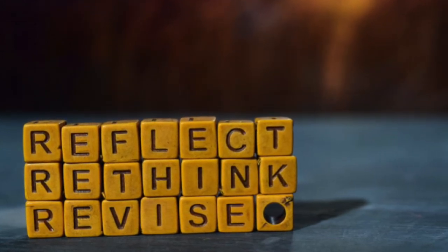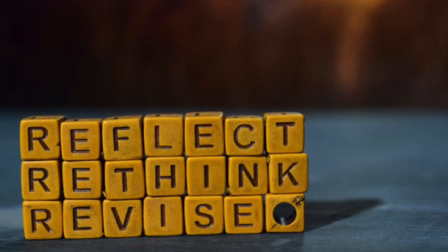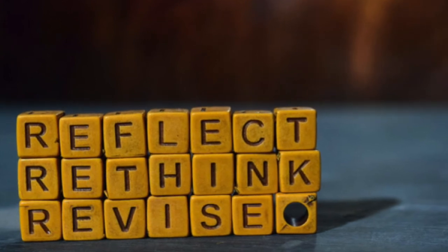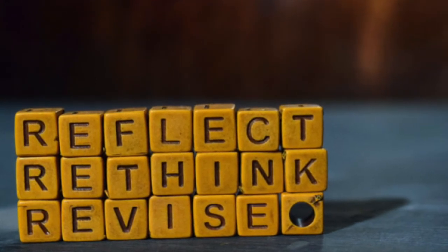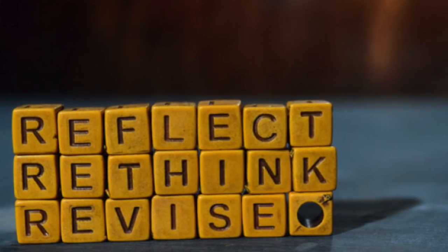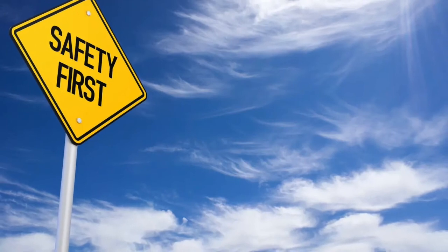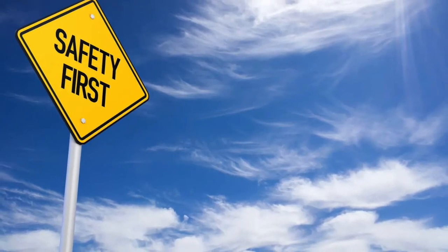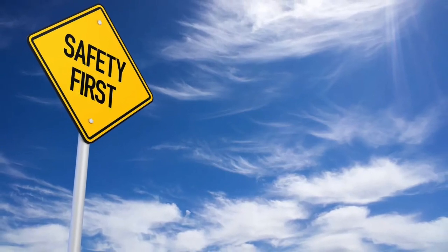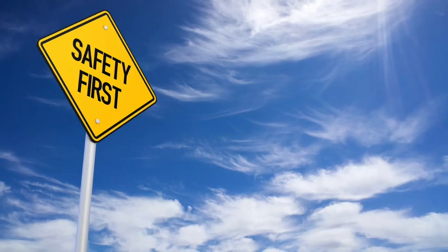I'm not sure if they did a tailboard. I'm not sure what they did. I know we did our tailboard and did what we were supposed to do, but these are the kind of things that, being experts in our field, if we can not only do our job, but kind of oversee what the others are doing, we might catch things like this before something can happen or somebody could get killed, because someone could have got killed. If somebody was on that neutral or on that ground in that building working or touching anything metal in that building that was grounded, they would have got shocked.